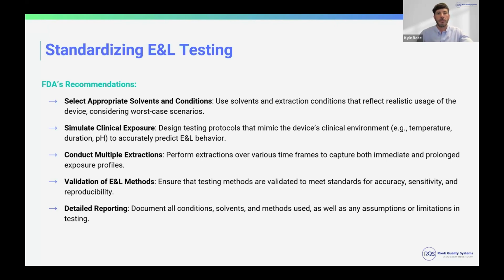Simulate clinical exposure, so designing testing protocols that mimic the clinical environment, temperature, duration, pH, things like that, of where it will be used in the body. Conducting different types of extractions, so performing extractions over different time frames for both immediate and prolonged profiles.